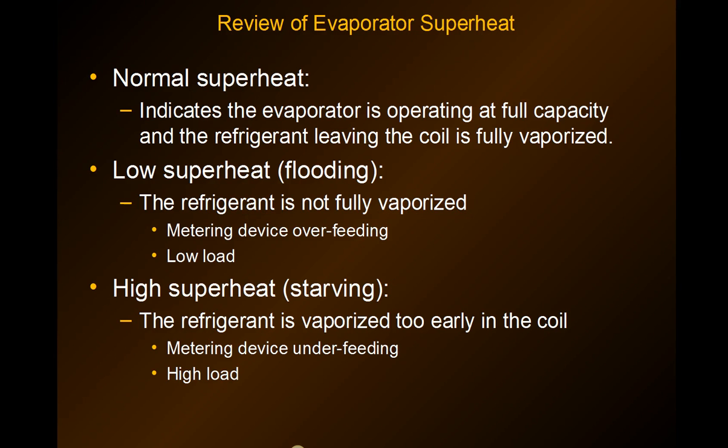Superheat. Normal superheat indicates that the evaporator is operating properly and at its fullest design capacity, and that the refrigerant leaving the coil is totally vaporized — all vapor — so that we don't send liquid back to the compressor.